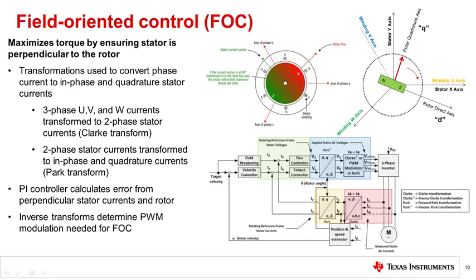Finally, the controller output voltages VD and VQ and inverse Clarke and Park transforms are used to convert back into the three-phase reference frame. The modulated PWM phase voltages VU, VV, and VW feed back into the inverter to drive the motor.